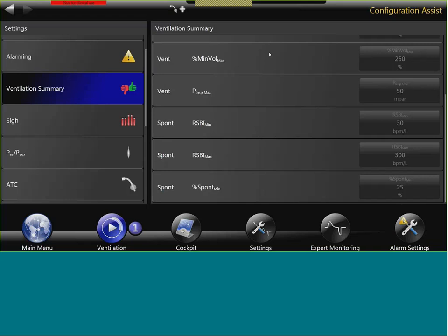It's not possible to adjust these values again. So you can only readjust or change the values after ventilation or when the ventilator is in standby. That's so that no one can cheat and keep a patient in an extubation area where he might not usually be. That's the reason why you can't adjust it during ventilation.